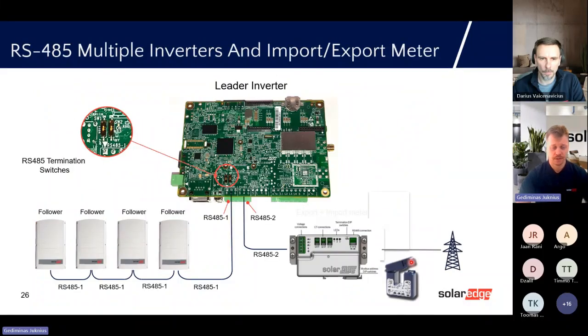With the communication, if you do an installation with multiple inverters and you do it for the first time, please do not hesitate. Text us, write us, we'll help you, we'll explain it if you need it. We'll give you a call and help you on the site. But two things to remember. First of all, never ever forget to turn on the RS-485 termination switches for the first and the last inverter in the row. Make the leader an inverter, not any other device. Do not make the leader the gateway. Do not make the leader anything else. Make the leader an inverter, and then the rest are followers. Very simple, easy to remember.